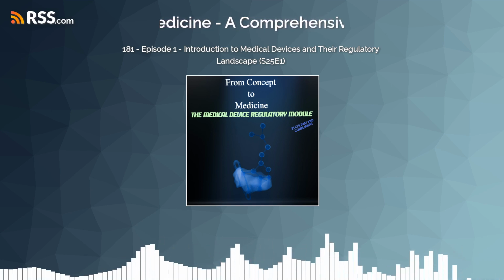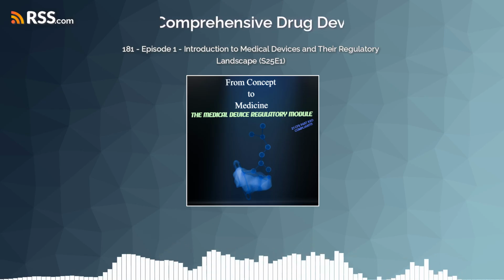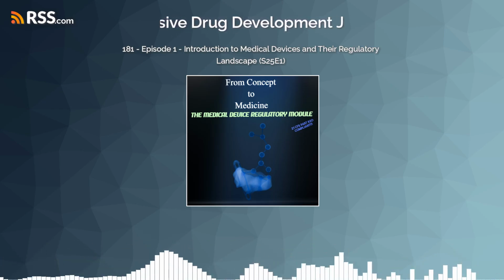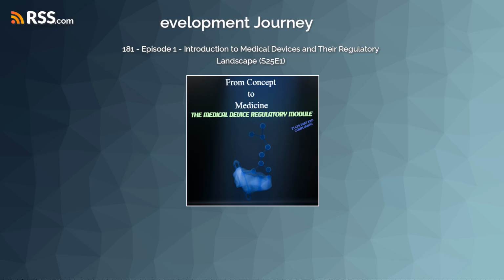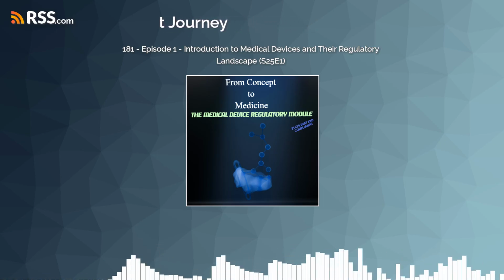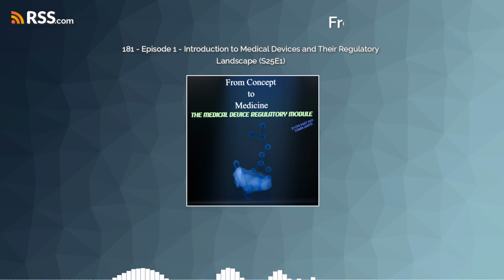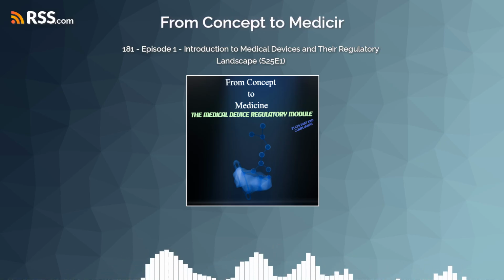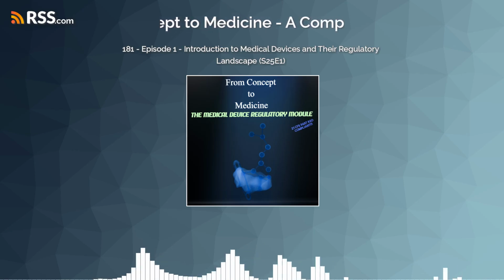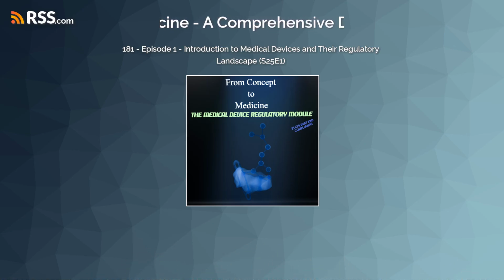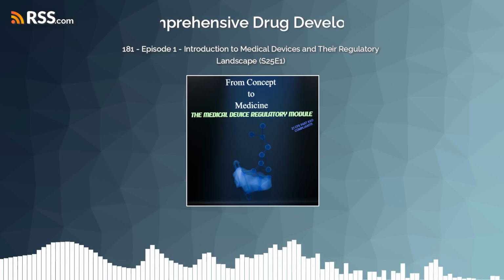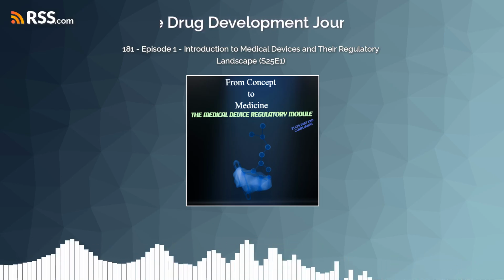It mandates a robust quality management system, or QMS. QMS. And this QMS has to encompass pretty much everything. Design, purchasing, manufacturing, packaging, labeling, storage, installation, servicing, and post-market activities. The goal is to ensure devices consistently meet their specifications and safety and effectiveness standards. And is there an international standard that aligns with this QSR, maybe helps global manufacturers?